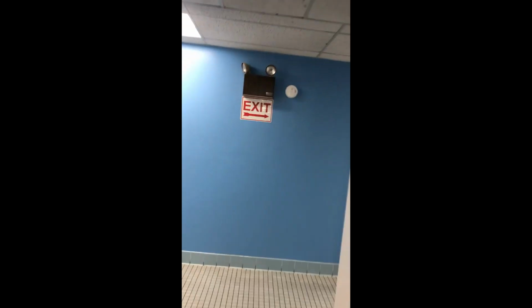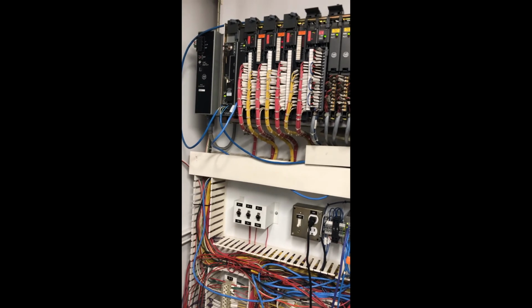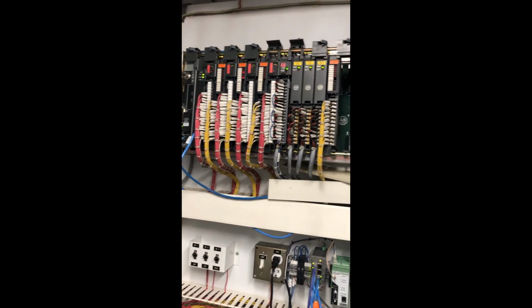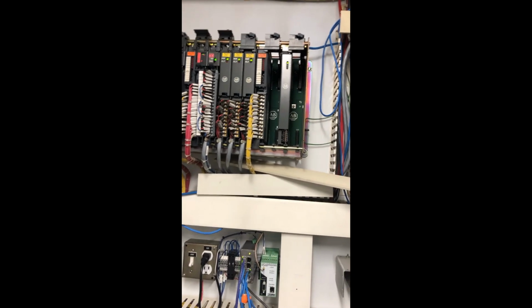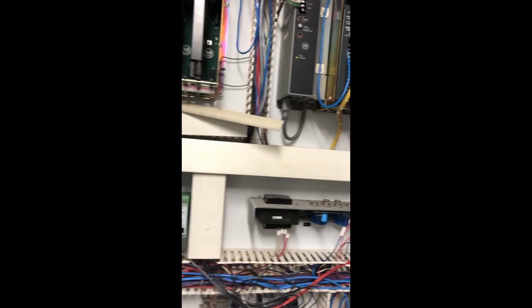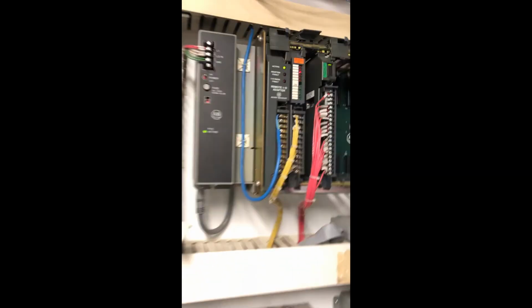But like I told you before, the real nuts and bolts is really in the PLC and the PLC programming. So over here in my office, I'll just kind of bring that up real quick. And here is the PLC for the filter side, the clean side. This is where the secondary clarifiers are, the filters, the disinfection, and a lot of other stuff. Aeration, I think, is over here too. Not quite as much I/O. There's the PLC there, and it's a host rack, and then a little bit of I/O in this remote rack there.